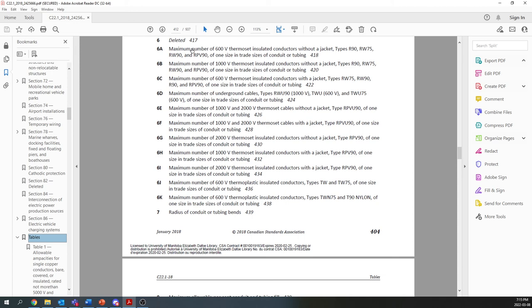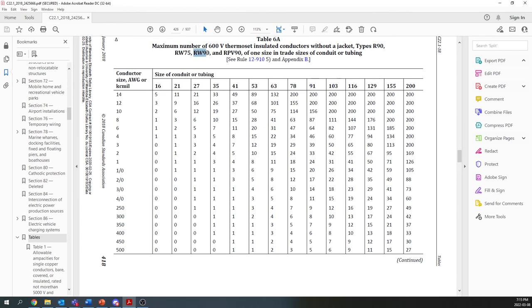So we're using RW90 wiring. I didn't actually say that, but that's what we'll be using. So this table does not really exist anymore. What you have to do now is look up the cross-sectional area of each of your wires and the maximum fill for a conduit. You add up the cross-sectional area for your wires. You derate the conduit size by the maximum fill, depending on how many wires there are in the conduit. And then, via the sizes of conduits that are provided, you calculate what conduit size you need. In this case, we're just going to go by this chart here, which is the old way of doing it.